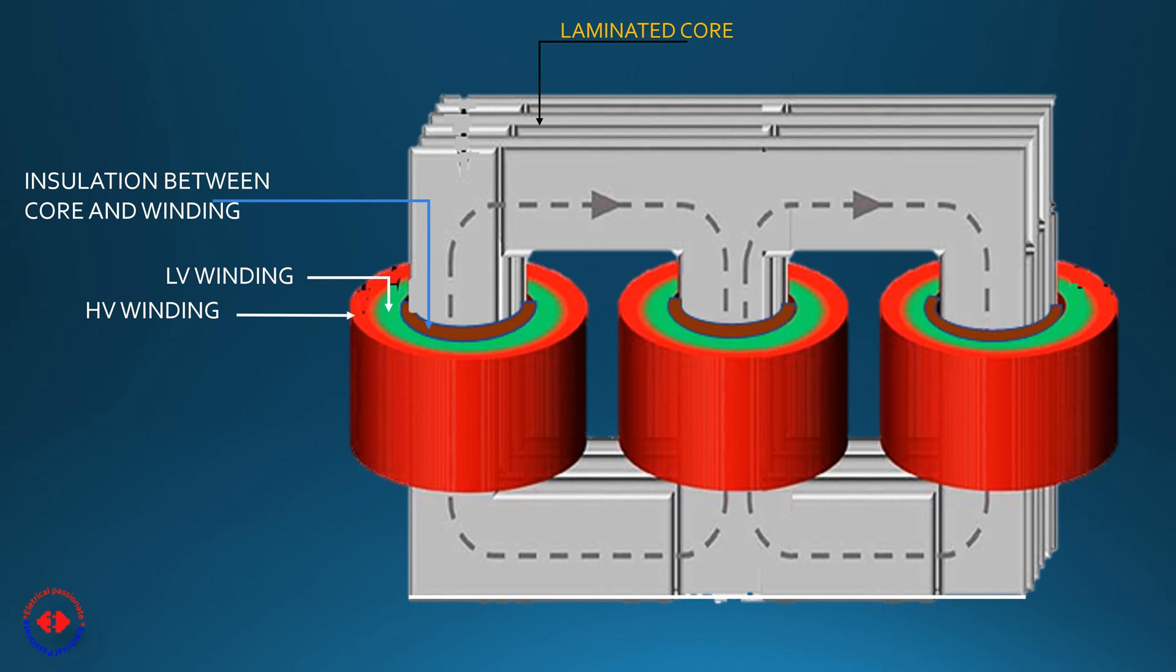LV winding is placed near the core due to its low voltage and thus less requirement of insulation between them. Both HV and LV windings are insulated with each other and with the core.